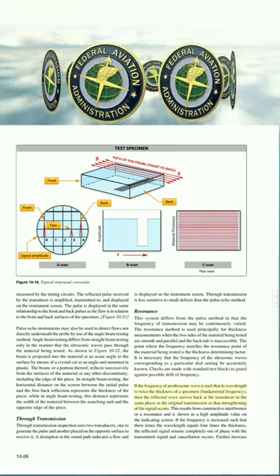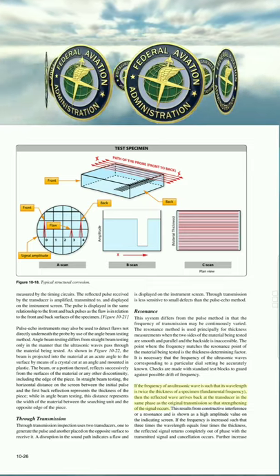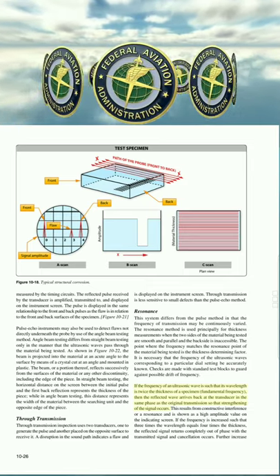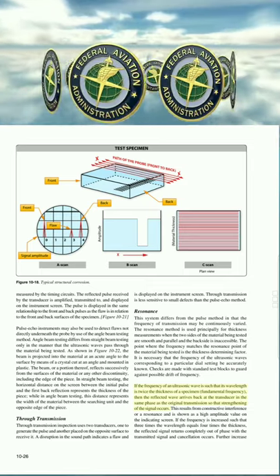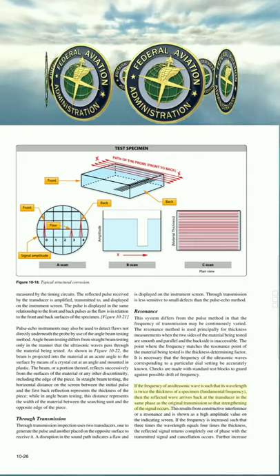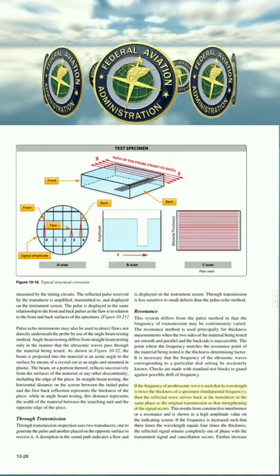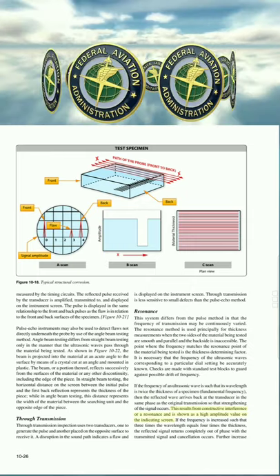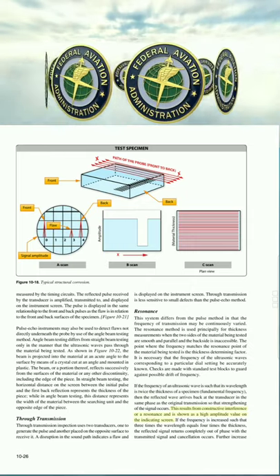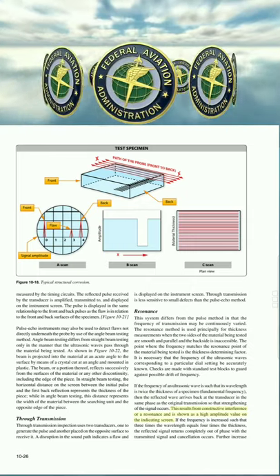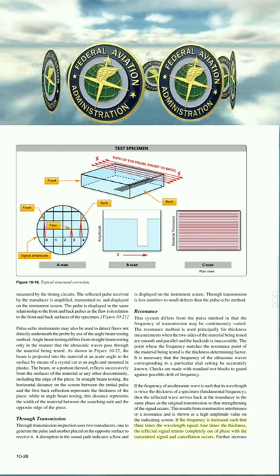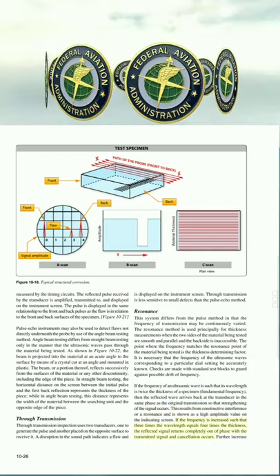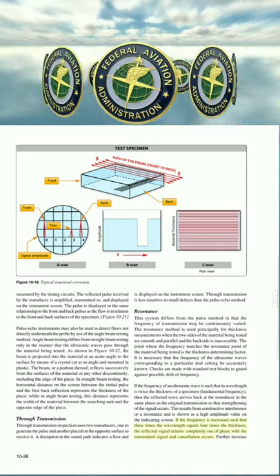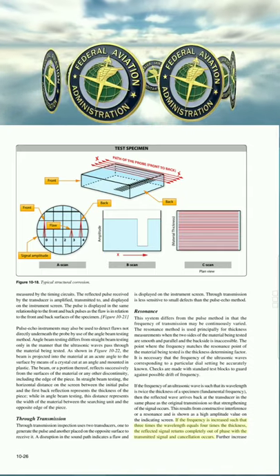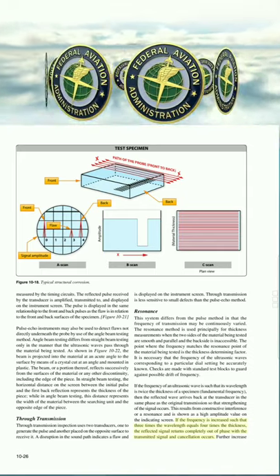If the frequency of an ultrasonic wave is such that its wavelength is twice the thickness of a specimen, the fundamental frequency, then the reflected wave arrives back at the transducer in the same phase as the original transmission, so that strengthening of the signal occurs. This results from constructive interference, or a resonance, and is shown as a high amplitude value on the indicating screen. If the frequency is increased such that 3 times the wavelength equals 4 times the thickness, the reflected signal returns completely out of phase with the transmitted signal, and cancellation occurs.